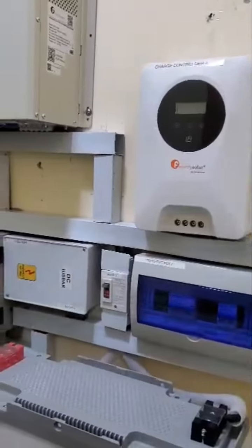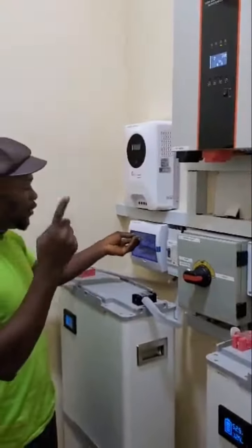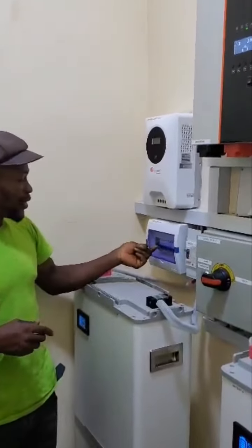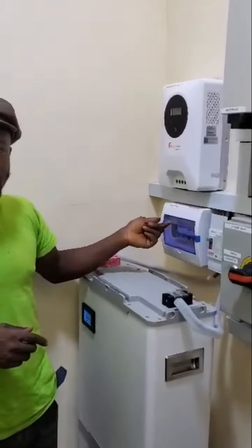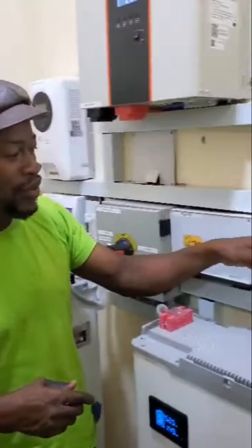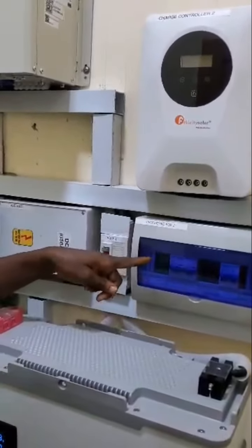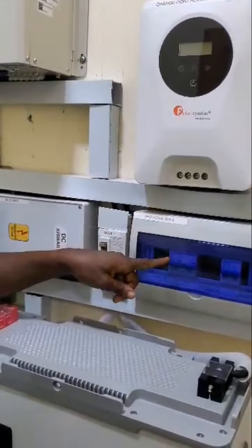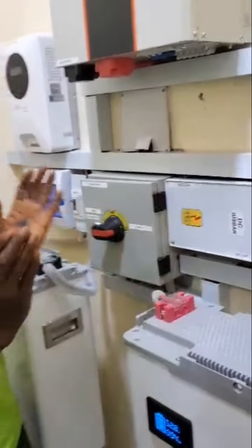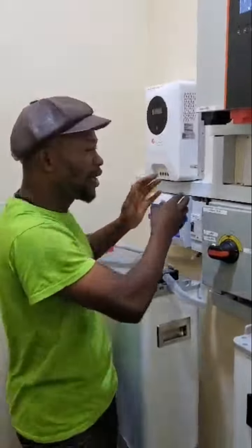This is because the input PV voltage needs to be protected with a circuit breaker. We have been able to protect it with a 120 amps circuit breaker alongside the DC surge. I'll also take you over to protective box 2, together with the DC surge and the protective circuit breaker. What comes into these two boxes are separate arrays of PV modules. Up in the installation, we have separate arrays that come into the system.